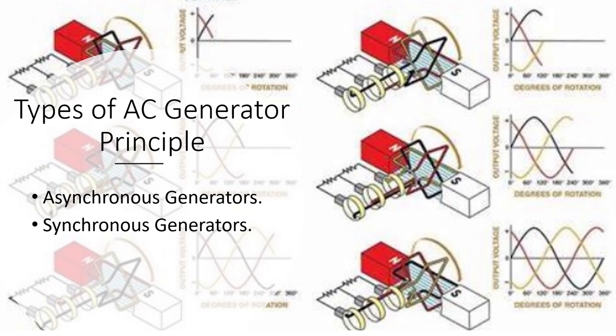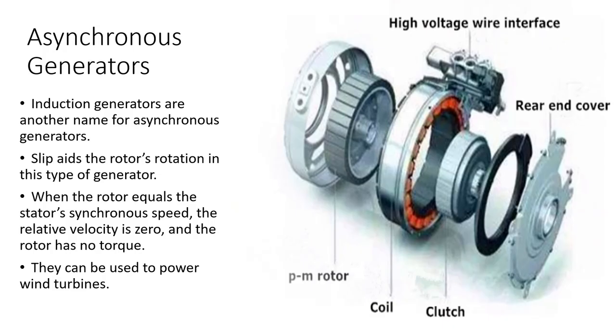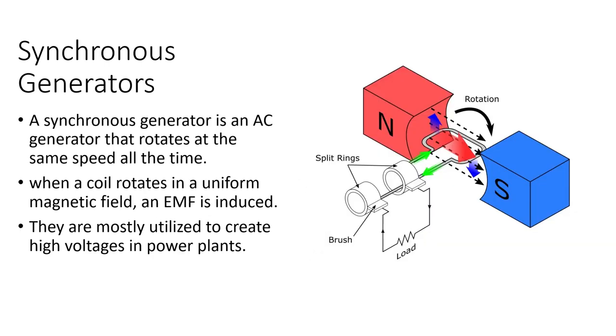Types of AC generator according to principle: one is asynchronous generators, and two is synchronous generators. Induction generators are another name for asynchronous generators. Slip aids the rotor's rotation in this type of generator. When the rotor equals the stator's synchronous speed, the relative velocity is zero and the rotor has no torque. Asynchronous generators can be used to power wind turbines.